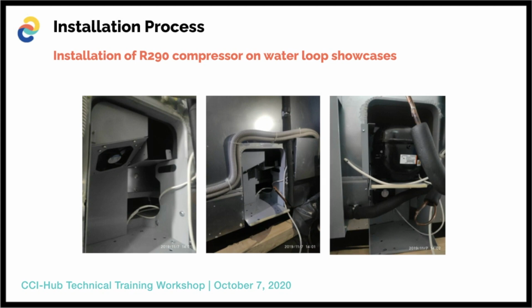The cabinets have 3 compressors. Actually, if you look at the cabinets, you can see 3 compressors with 3 separate circuits, especially on larger capacity units like upright chillers and glass door freezers. In self-contained equipment, there is only 1 compressor, the same as with R290 compressors.